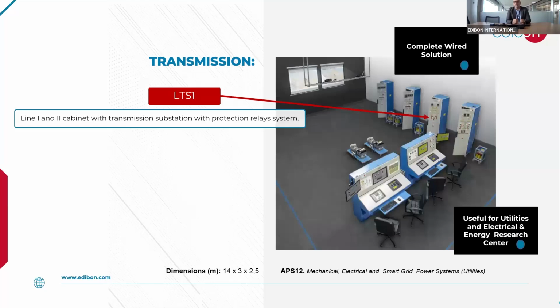We are using the most advanced multifunction protection relays with all functions like differential protection, distance protection, overcurrent, undervoltage, overfrequency, everything. Mostly we use SEL relays, but it's customizable. If a customer requires GE, Schneider, or ABB, we can change the relay according to their requirement, since some customers want most of their assets in the power plant or system from one brand. We try to do it, because most multifunction protection relays are similar, just different in configuration.